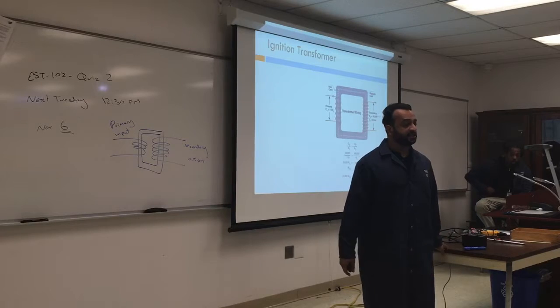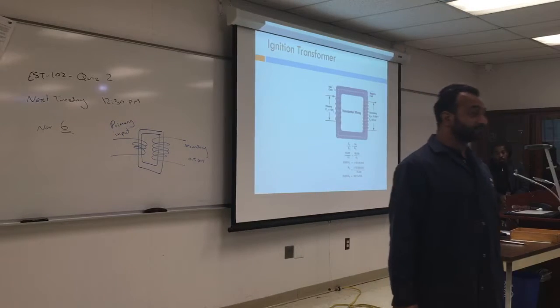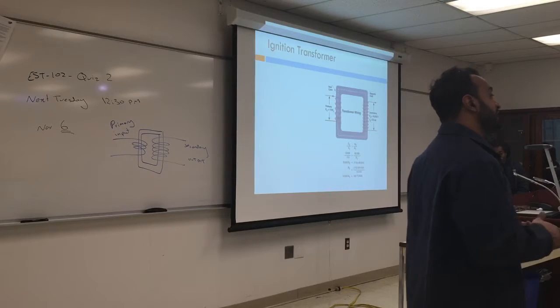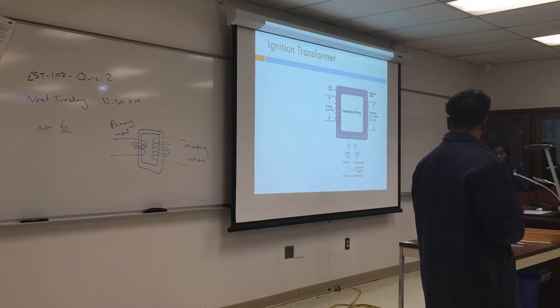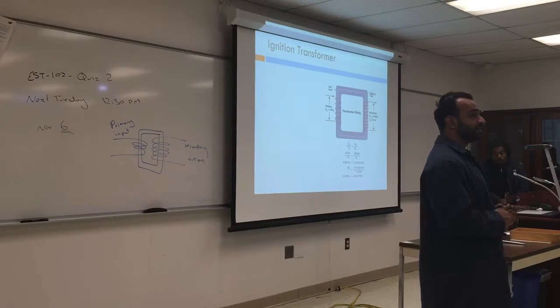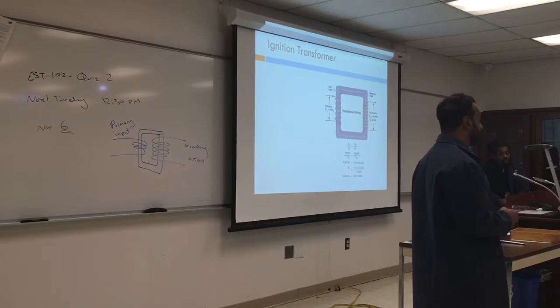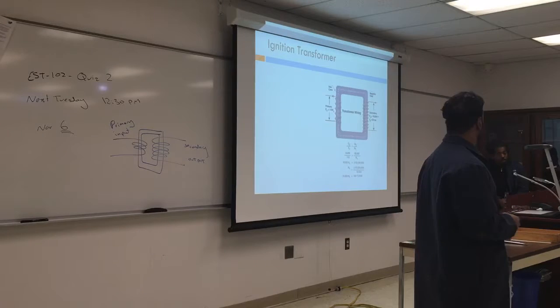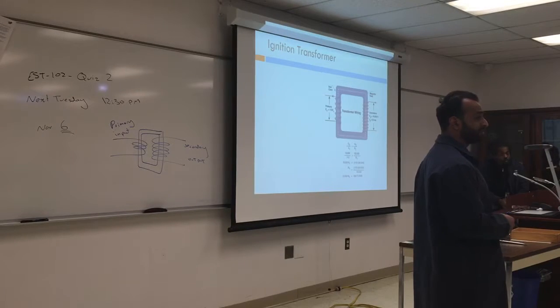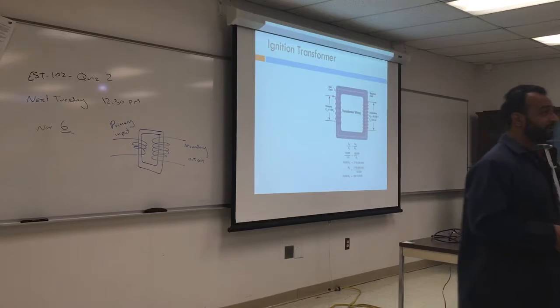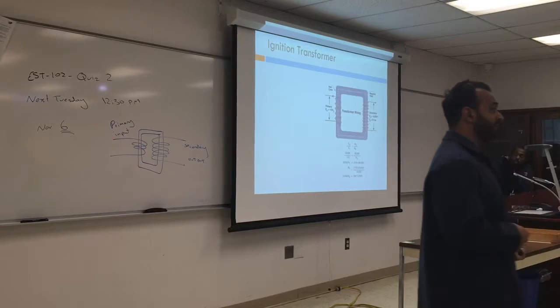This transformer is sealed, you're not to fix it. It's completely done, and it's sealed with tar or wax. You just test its output and input. If it's bad, you have to change it. They're not cheap, they're expensive, around $150 to $200. However, they are very reliable, they last for a long time, and they give enough power.